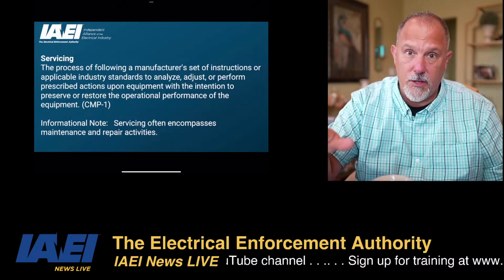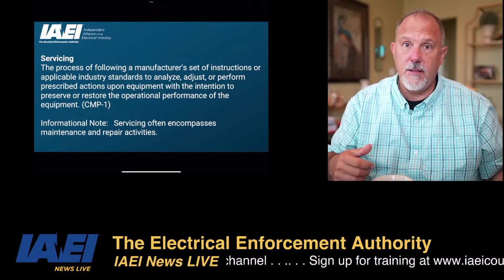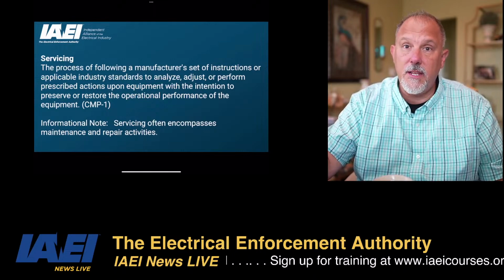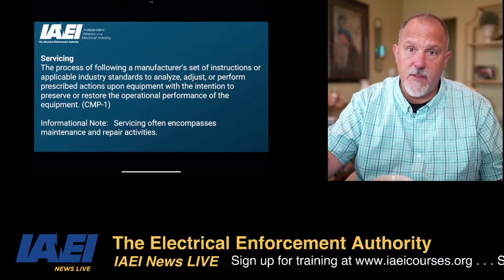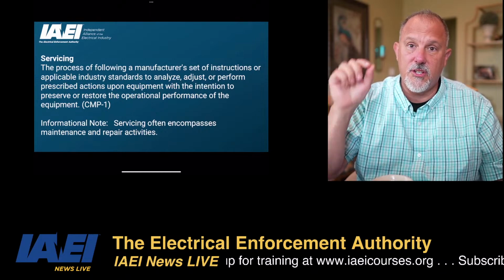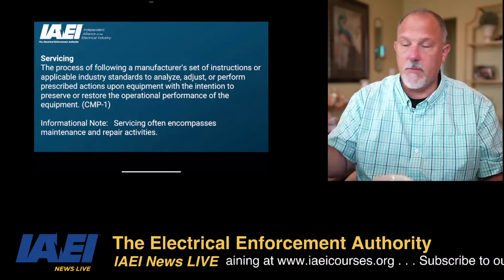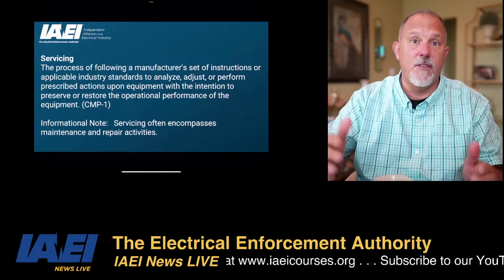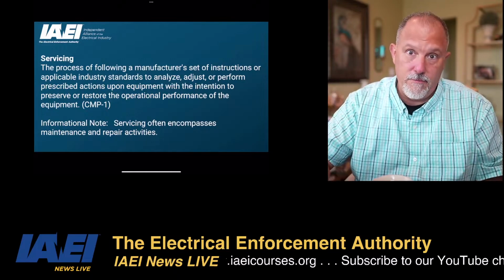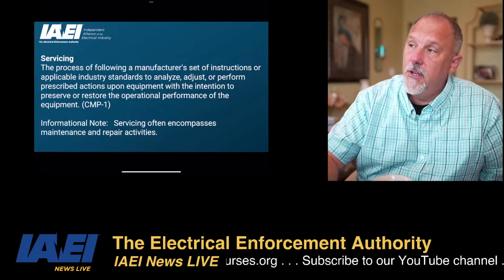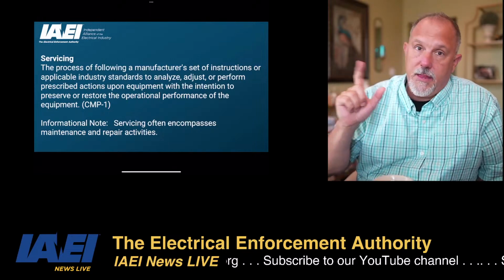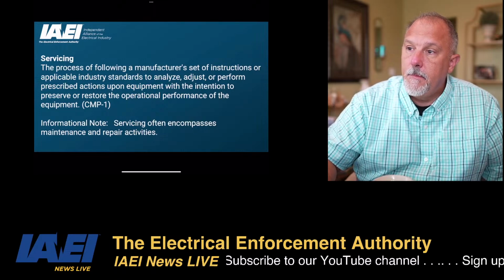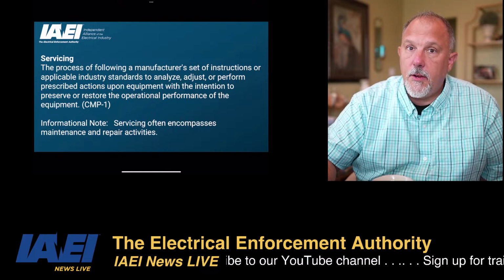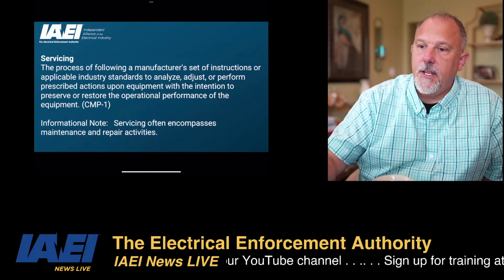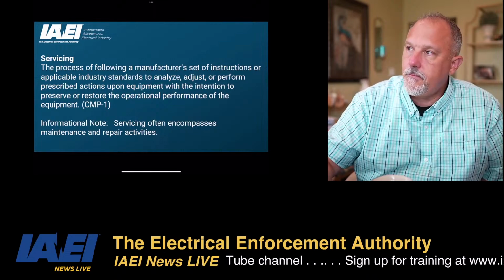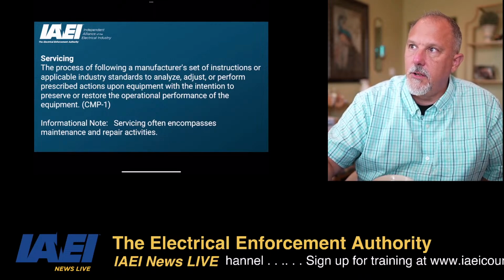So Daryl, regardless of what you feel about reconditioning or servicing, anything you do to an existing transfer switch, whether it's Article 700, 701, 708, as long as you're not installing a transfer switch that has been reconditioned, you can recondition it, you can service it, you can do anything you want to it because of that language being proposed for the 2026 code cycle. I think it needs to be fixed. But your point on the difference between servicing and reconditioning is very compelling, and we need to really take a close look at that. That's a very good point.